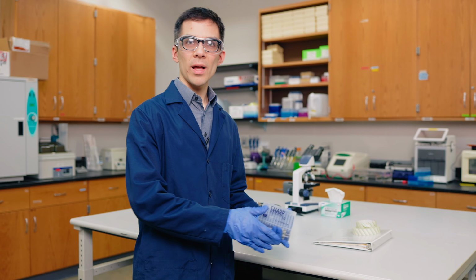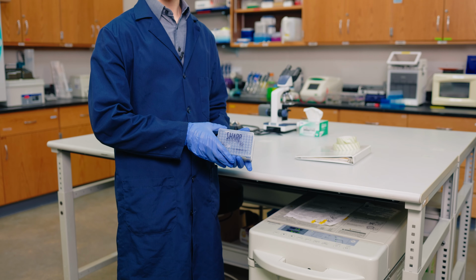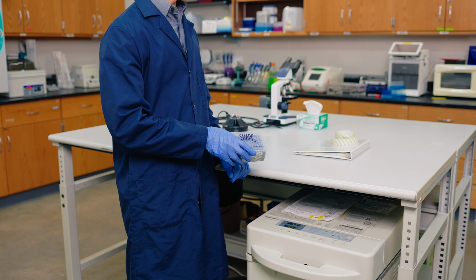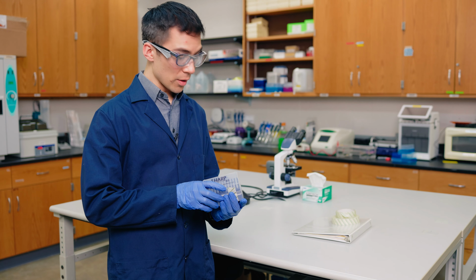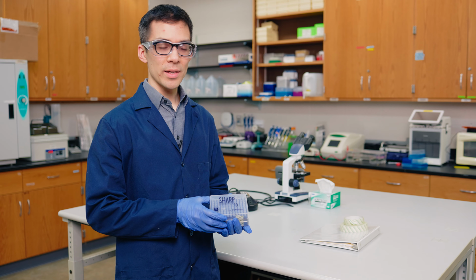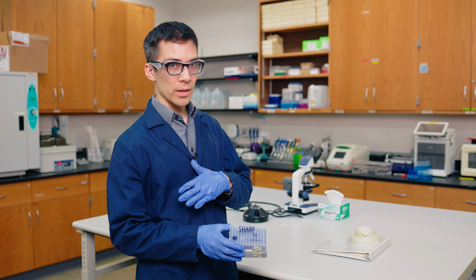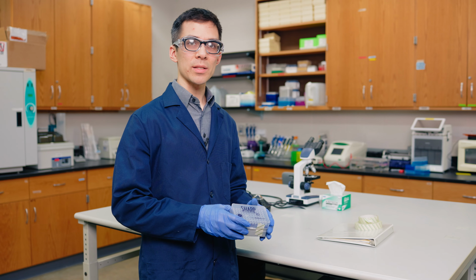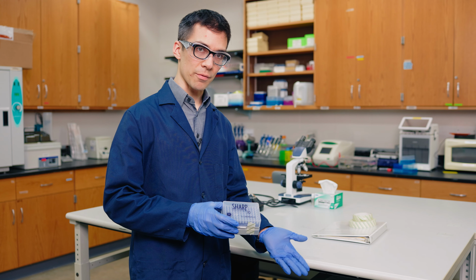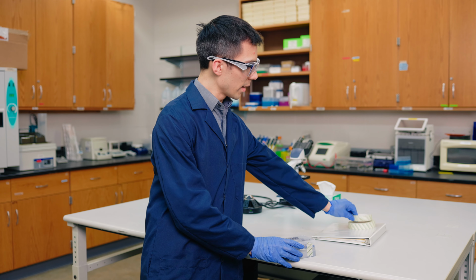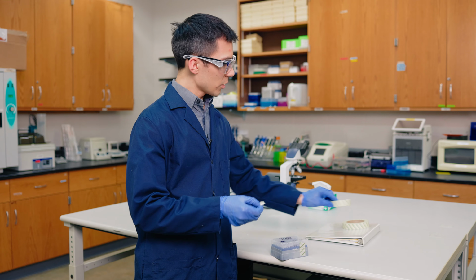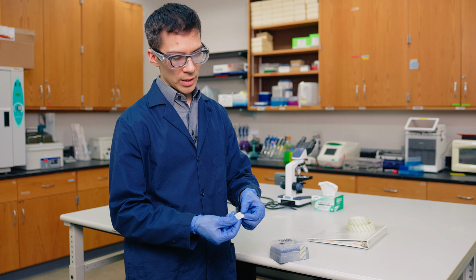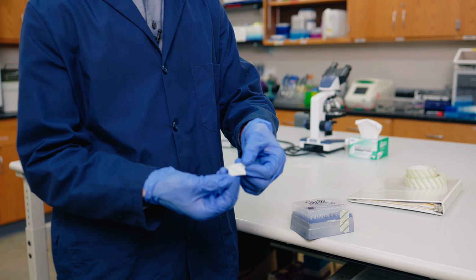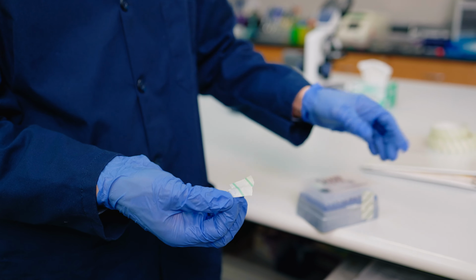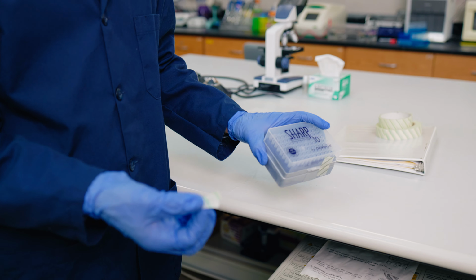The autoclave sterilizes things by raising them up to a temperature that kills any microorganisms. We want to make sure we know when things have been properly sterilized, both so that we can tell the difference between sterile and unsterile objects, and also just to confirm that the autoclave cycle worked properly. And the way we do that is with autoclave tape. So the autoclave tape just has these stripes on it. The stripes look light green before they've been heated, and then after they've been heated, they turn dark green.